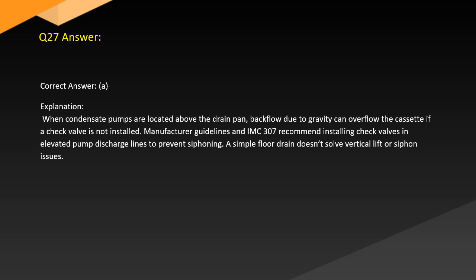Answer. Correct answer, A. Explanation. When condensate pumps are located above the drain pan, backflow due to gravity can overflow the cassette if a check valve is not installed. Manufacturer guidelines in IMC 307 recommend installing check valves in elevated pump discharge lines to prevent siphoning. A simple floor drain doesn't solve vertical lift or siphon issues.